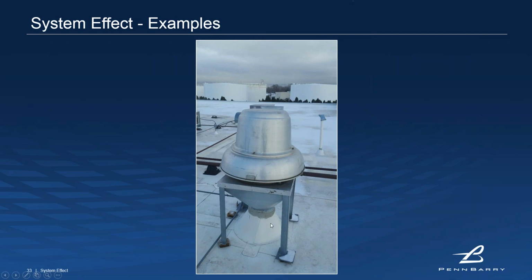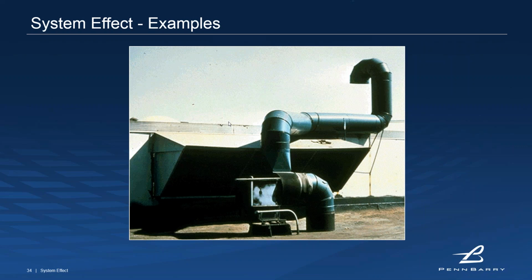I don't know what's going to happen in this fan, this one here with this Venturi here, but you can imagine that there are better ways to accomplish that that don't have reductions and then immediate expansions right in front of the fan. Who knows what's going on here, but this is a lot of interesting ductwork, and it's all hanging out right in front of an air handler intake, presumably.